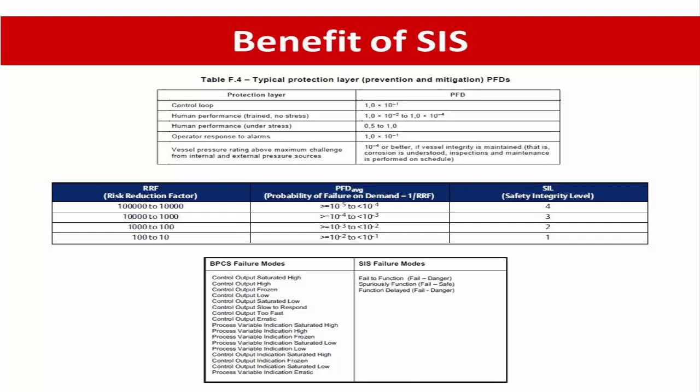In the picture, you can see the PFD average is lower than 0.1 for the SIS. The reason the BPCS has a higher PFD than the SIS is that the BPCS operates with signals that are relatively dynamic. This makes BPCS failures more frequent but detectable by people. The SIS, however, acts only when a potential dangerous condition is detected, which makes failure modes of the SIS very hard to detect.